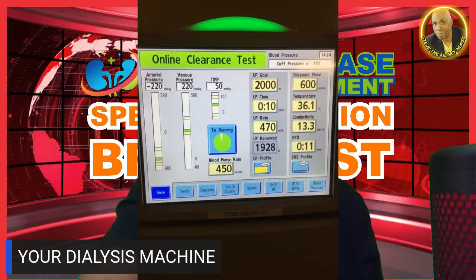So let's look at some additional safety checks. May look like this. Checking that the transducer is protected. This is a transducer, this filter right here. Are fluid and blood free for accurate arterial and venous pressure readings. You see these filters right here, they read the pressure. And you don't want them to get wet. One right here and one right here. You may see blood in this line if you're a patient at your unit sometime. Also, this prevents the machine internal transducer from becoming wet and contaminated.